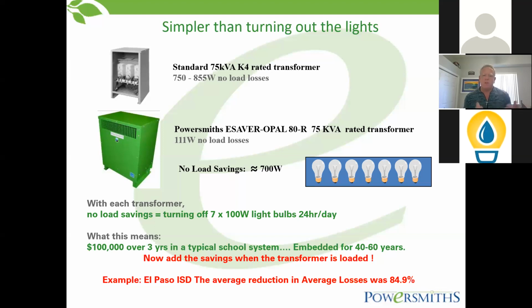So they're sitting there - our transformer is about 111 watts of no load losses. It won't come out of the factory if it's anything higher than that. So if you look at that, it's approximately 700 watts. It's like having 7 100-watt light bulbs on forever, just sitting there on. And this is just one transformer now, just sitting on.